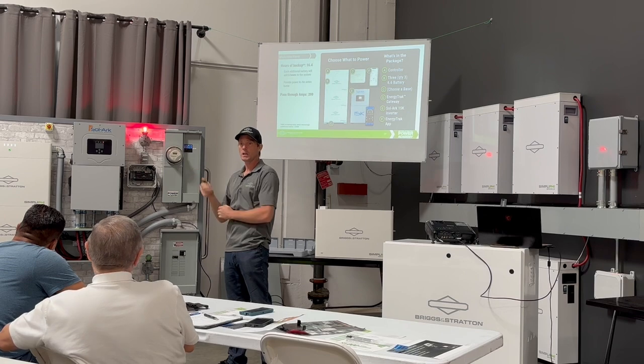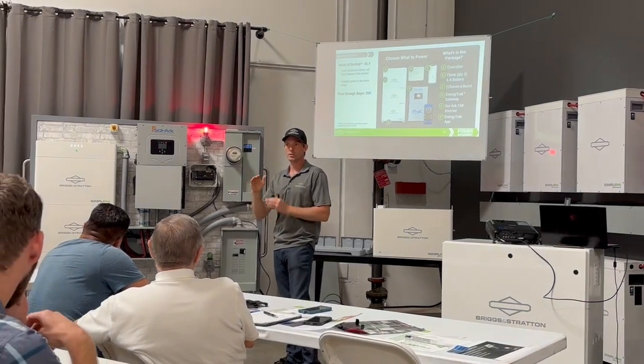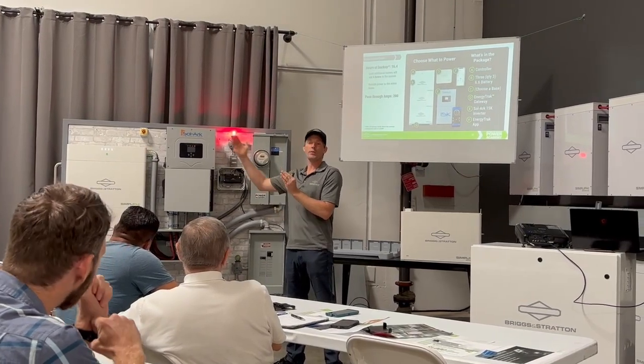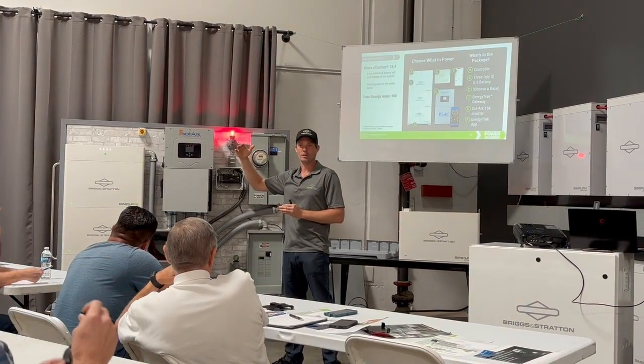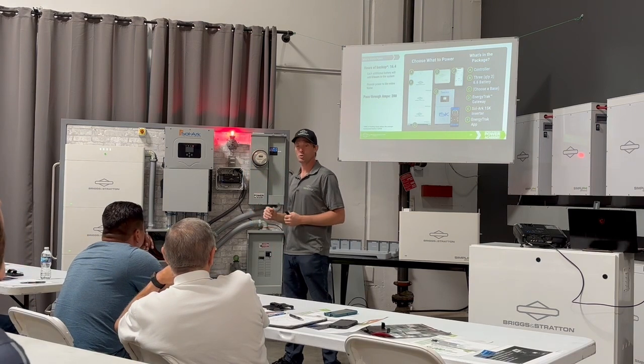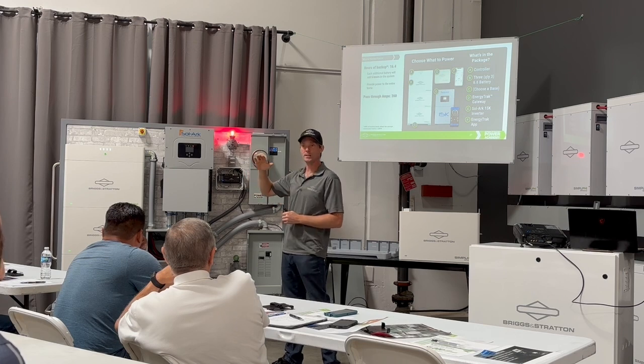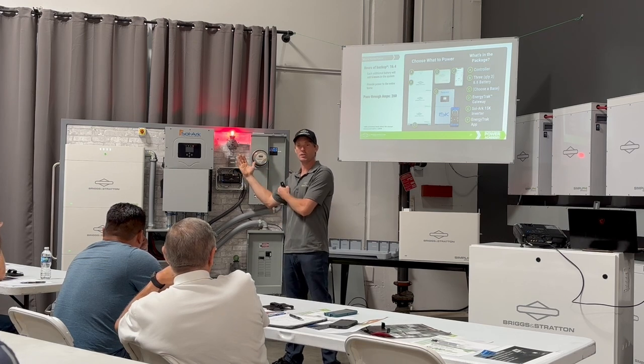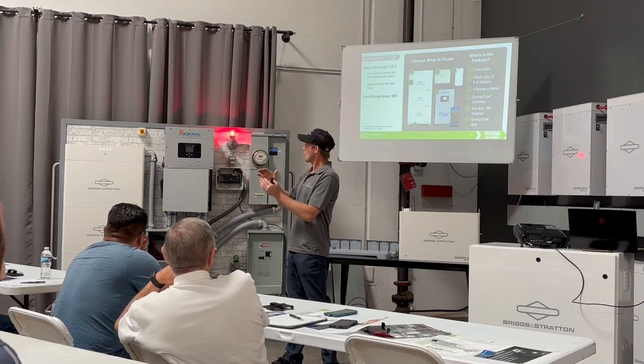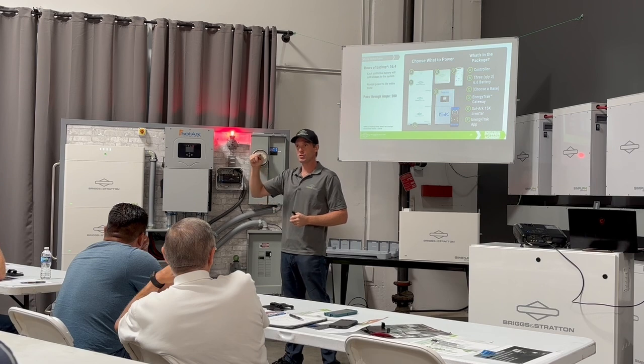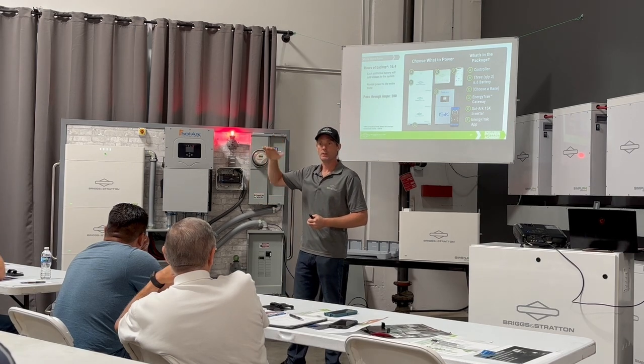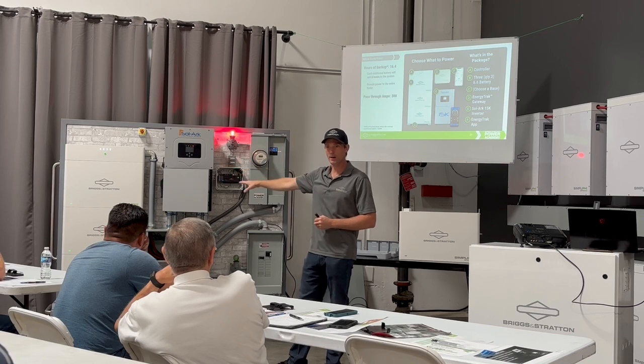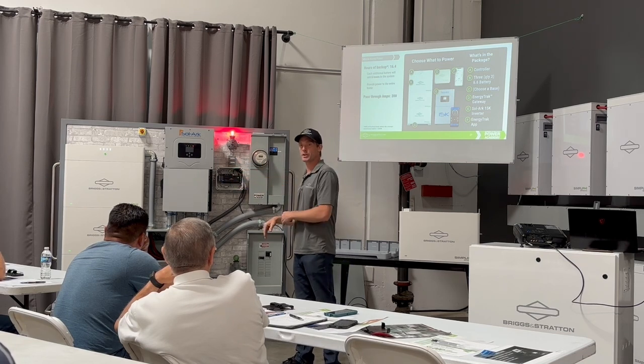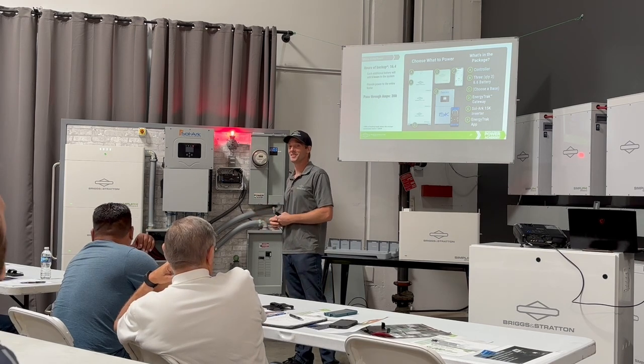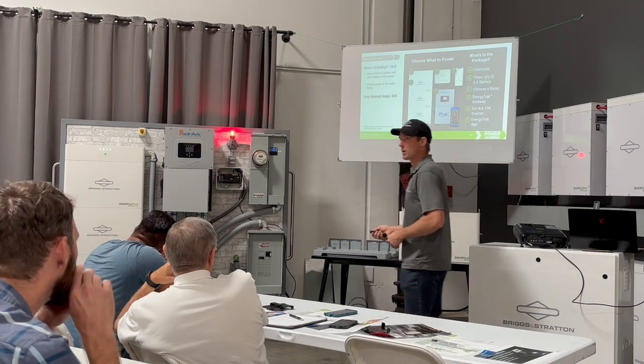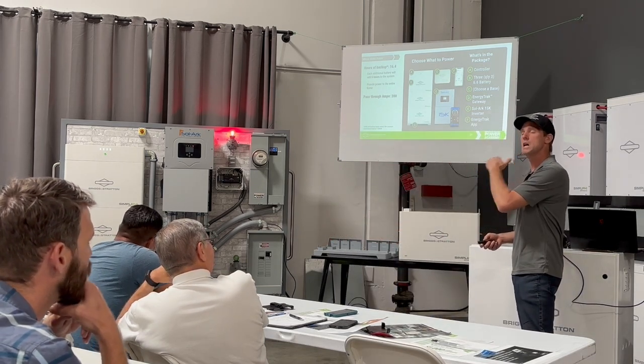With a Sol-Ark 15K, if it starts to backfeed, here's what happens on the grid versus a generator. When you start backfeeding the grid, nothing happens to the voltage. The grid is essentially stable, inert to us pushing a little bit. So the inverter leads the phase of the grid electricity a little bit and pushes electricity back to the grid. That's how it backfeeds the grid. When you try to backfeed a generator, the voltage regulator in the generator starts to rise, and this stops the backfeeding. So you don't have to worry about the Sol-Ark backfeeding your generator or the grid. It won't do it. It's smart enough to know that if that voltage goes up as it starts to backfeed, to stop backfeeding.